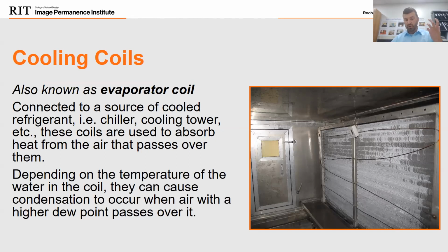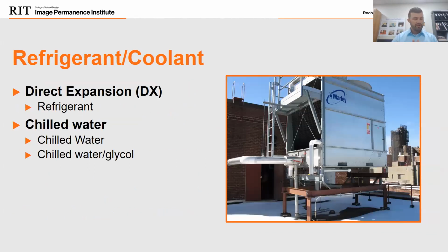So if we want to wring that moisture out and get our dew point back down, this coil has to be at least at a 50-degree dew point for us to lower it, remove that moisture, and cause condensation, getting the moisture we want out of the air. So, quickly, we discussed the refrigerants. There are two major types of refrigerants that we come across. There's DX, which is direct expansion.